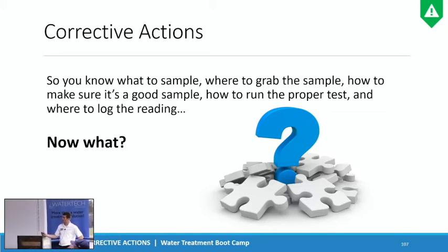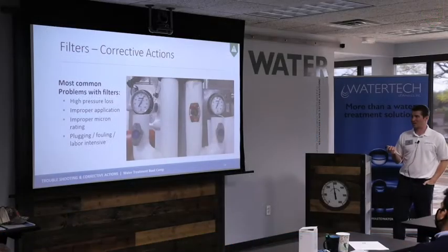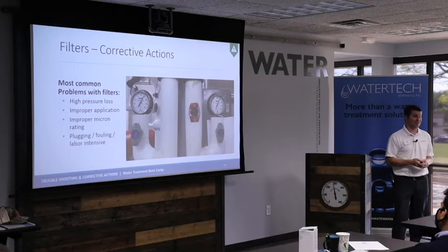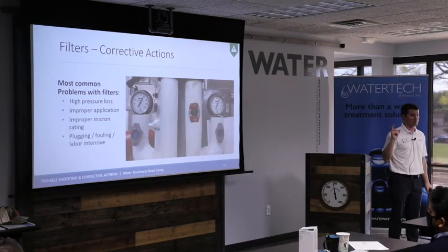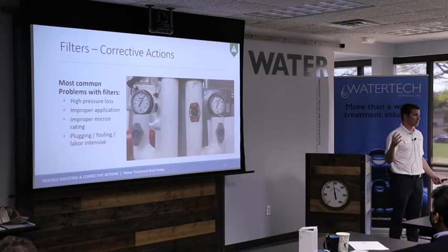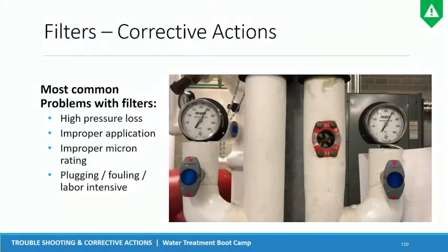Okay, so most common problems associated with filters, right, is again, high pressure loss. You let the filter run too long. Improper application. So when I say that, again, maybe you selected a filter that's not rated for 180 degrees and you open up your filter housing and you're like, why is my filter disintegrating every time, right? Because it's not the right filter.